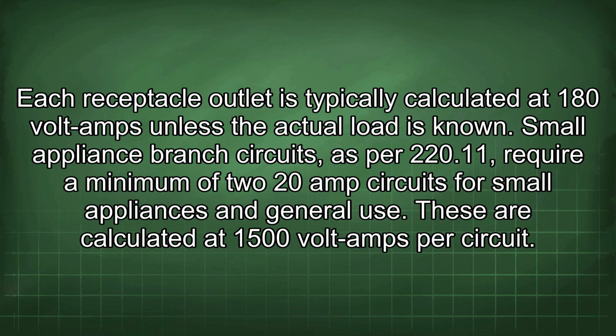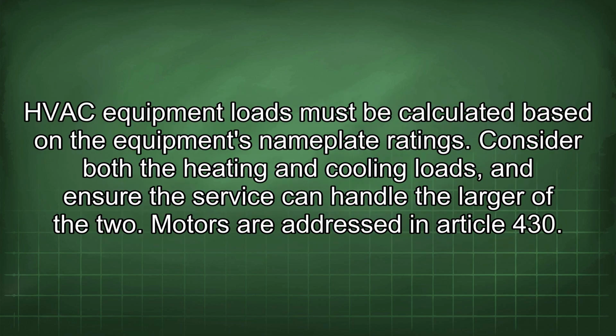Small appliance branch circuits, as per 220.11, require a minimum of two 20 amp circuits for small appliances in general use. These are calculated at 1500 volt-amps per circuit. HVAC equipment loads must be calculated based on the equipment's nameplate ratings. Consider both the heating and cooling loads and ensure the service can handle the larger of the two.